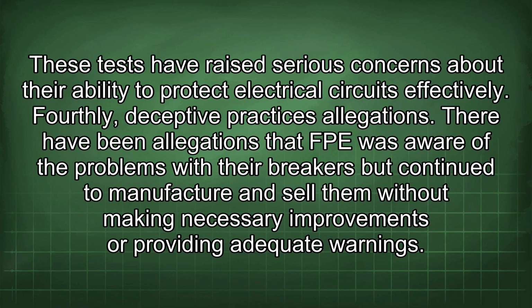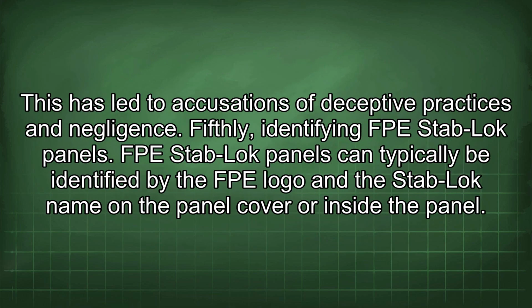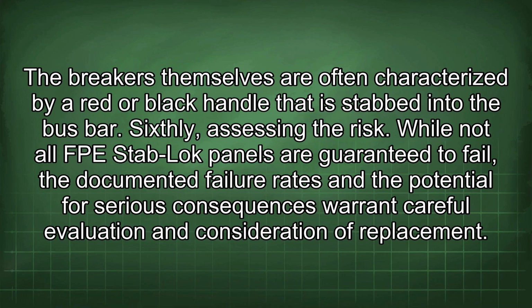Fourthly, deceptive practices allegations. There have been allegations that FPE was aware of the problems with their breakers but continued to manufacture and sell them without making necessary improvements or providing adequate warnings. This has led to accusations of deceptive practices and negligence. Fifthly, identifying FPE Stab-Lok panels. FPE Stab-Lok panels can typically be identified by the FPE logo and the Stab-Lok name on the panel cover or inside the panel. The breakers themselves are often characterized by a red or black handle that is stabbed into the bus bar.